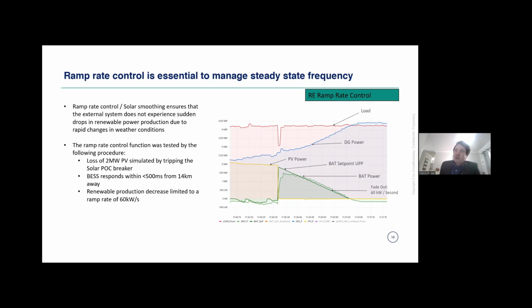Now, the reason I showed the network at the start was just to understand the complexity behind this application, because we didn't go with a co-located solar PV and BESS system, of which the reason I'll get into a bit later. So what this means was during a loss of PV, we had to ensure fast enough communication between the 2 points in the network, which is about 16 kilometers apart, which entailed the installation of a fast fiber ADSS link to allow our battery control system to respond within 500 milliseconds and inject the same 2 megawatt of power that had been lost and curtail then at a slower ramp rate. As we can see in the graphic, our generator was then able to slowly ramp up and not see the step change that was actually happening in the system.